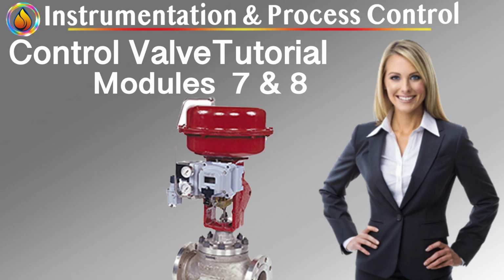Sources of friction. Friction is the silent enemy of control. Primary sources: packing compression, stem misalignment, seal drag, bearing wear, surface roughness. Friction causes deadband, no response to small signal changes, stick-slip motion, and limit cycles that look like tuning problems but are not. Positioners mitigate friction by applying corrective force quickly, but cannot eliminate it entirely.